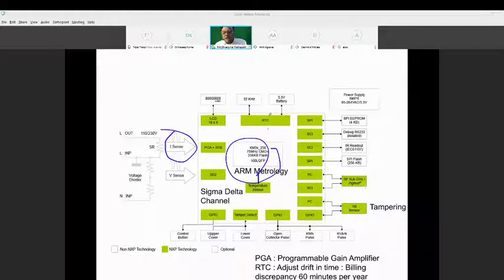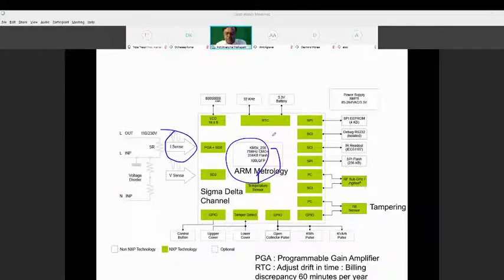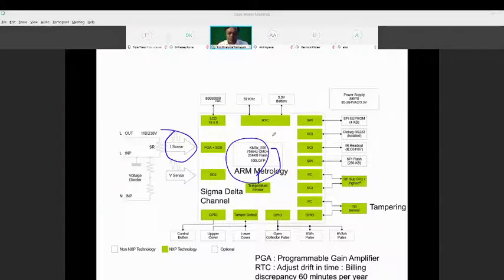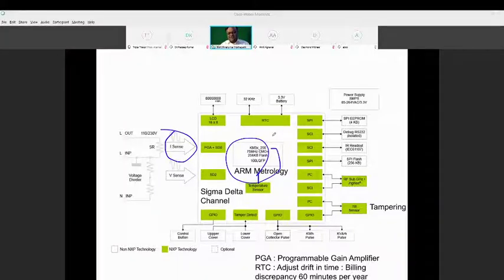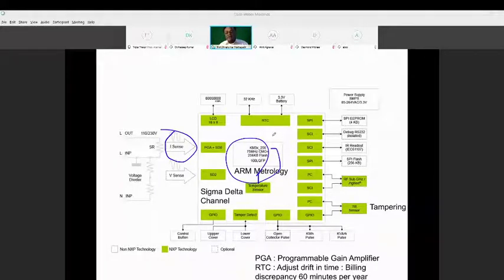There is a real-time clock. Over a period of one year, the time can drift by about 60 minutes because of all these components, so we need to adjust the timing. The real-time clock is there so you can adjust based on real time, otherwise the precision of billing goes wrong. The tariff is also time-scheduled - night rate, morning rate, afternoon rate, summer rate, winter rate - so real-time operations are essential.